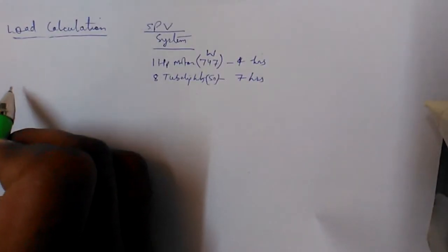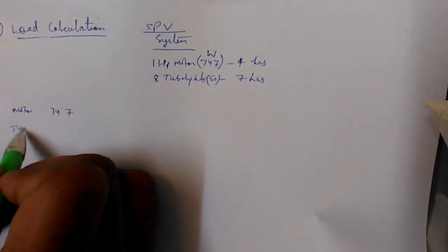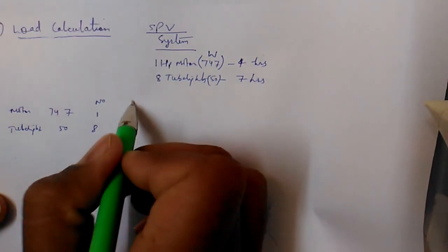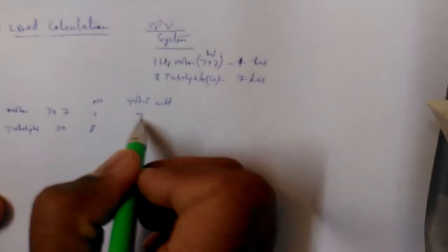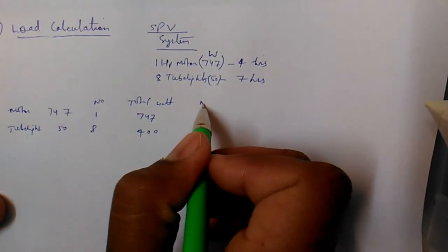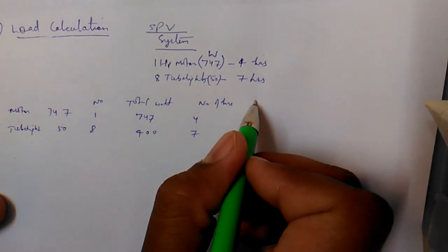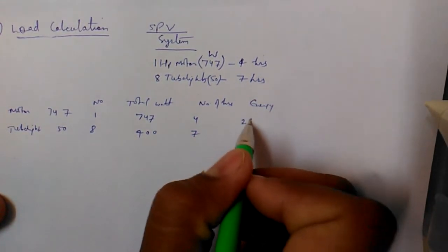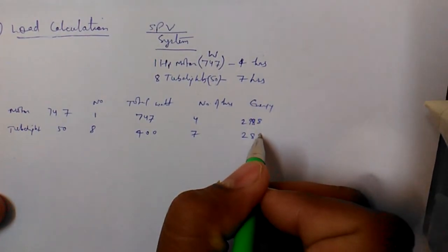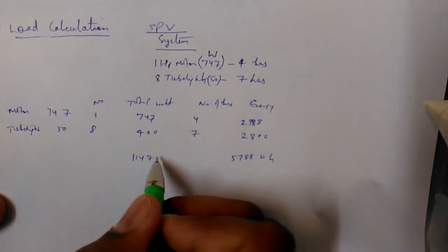First, we calculate the load. Motor: 747 watts, one unit. Tube lights: 50 watts, eight units. Total watt is 1147. Number of hours: four and seven respectively. Energy: 747×4 = 2988 watt-hours, and 50×8×7 = 2800 watt-hours. Total energy is 5788 watt-hours.